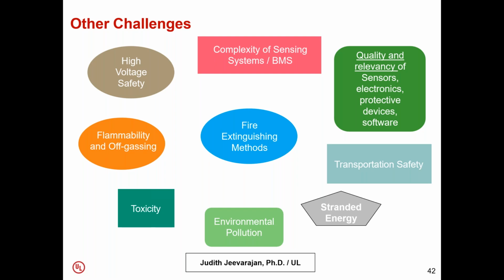Fire extinguishing methods have not been optimized for lithium-ion batteries. A lot of work has been done with different fire suppressants, and we find that copious amounts of water is the best fire extinguishing medium. But in the Indian environment, I've been asked if salt water is okay. You have to think about that, because it can cause a short circuit. If you pour salt water on a high voltage system, you could get arcing, sparking, and fire before the water dissipates all the heat in the battery and cools it down completely.